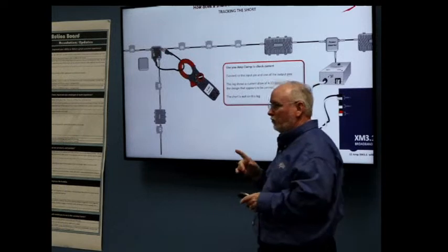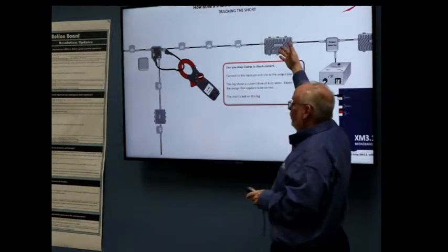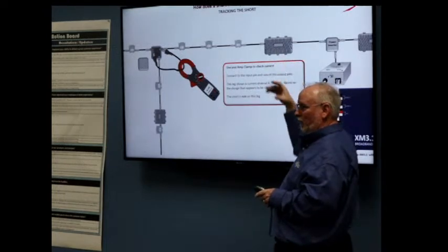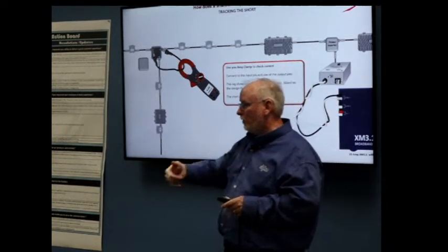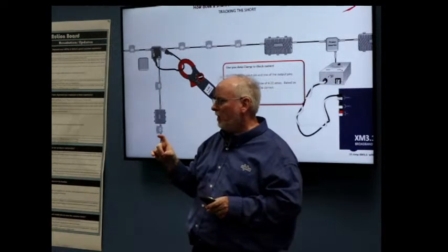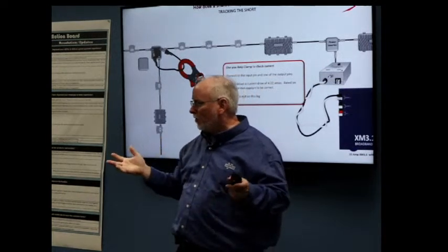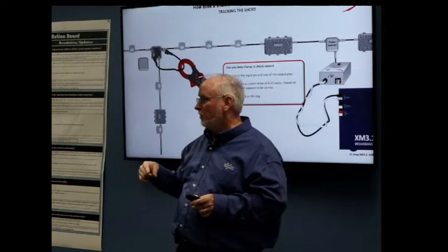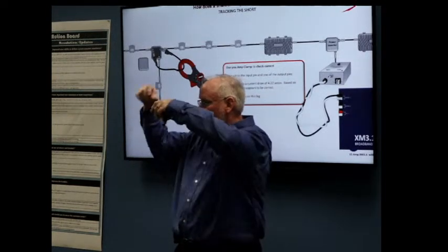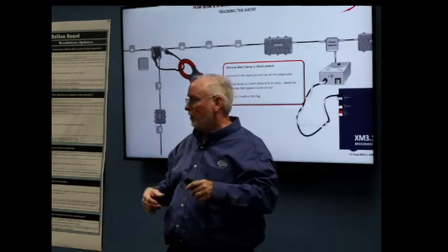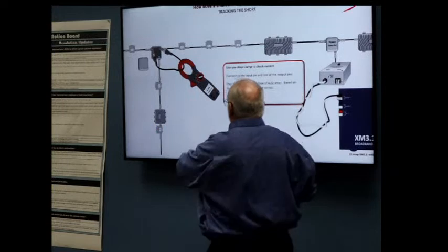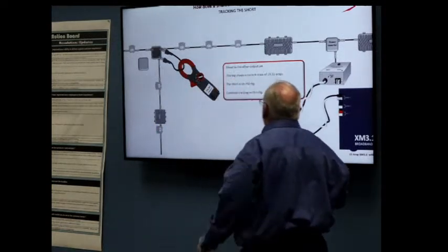Now, the one thing he did not show, I would have dropped the node face first and checked inside the node. There are devices you can get that will allow you to extend those, mostly the MDL plugs, which look like car fuses. They make extenders for those. So you can bring the extender out, put your clamp across it, check it in the node. Maybe there's something short in the node. This happens. But pull it off and just keep walking through the plant.